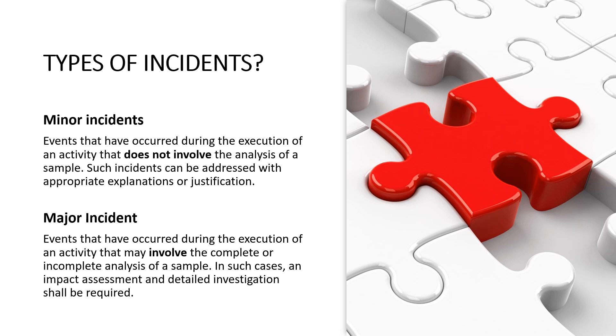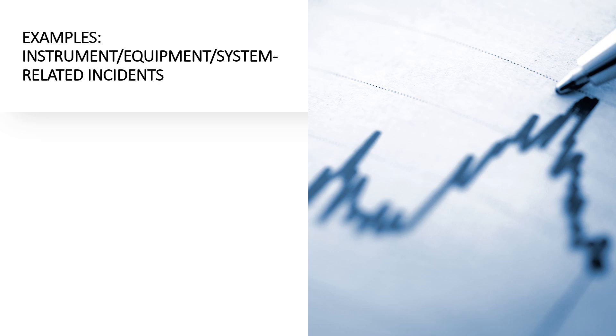Major incidents are those events that occur during the execution of an activity that may involve the complete or incomplete analysis of a sample. In such cases, an impact assessment and detailed investigation shall be required — meaning the incident may impact product quality and must be investigated. For example, when product analysis is performed on an HPLC instrument and the incident is observed after the injection or analysis of a sample, it shall be considered a major incident. Based on evaluation, we can decide whether an incident is minor or major.